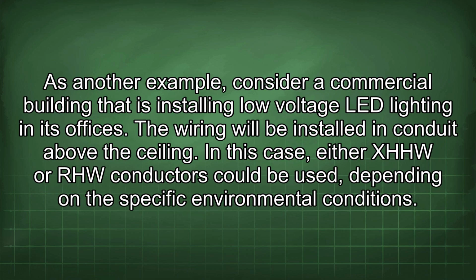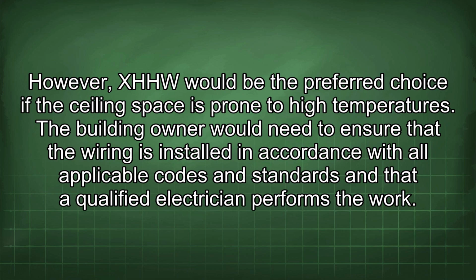As another example, consider a commercial building that is installing low-voltage LED lighting in its offices. The wiring will be installed in conduit above the ceiling. In this case, either XHHW or RHW conductors could be used, depending on the specific environmental conditions. However, XHHW would be the preferred choice if the ceiling space is prone to high temperatures. The building owner would need to ensure that the wiring is installed in accordance with all applicable codes and standards and that a qualified electrician performs the work.